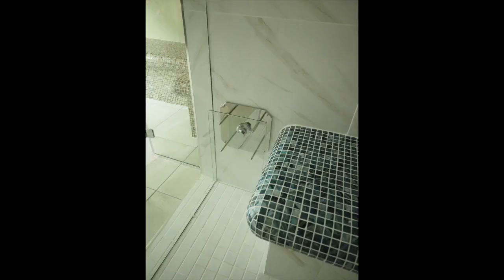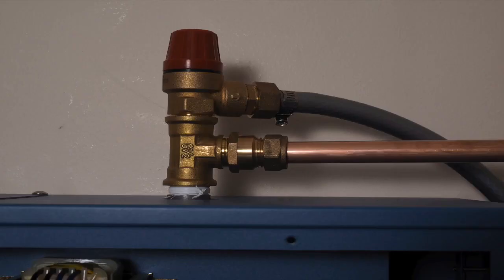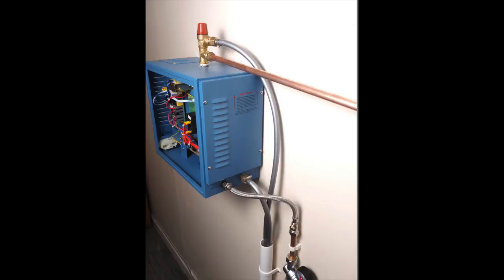The steam nozzle should be positioned 300 millimeters from the floor of the steam room and as far away from users' feet, a doorway, or the temperature sensor. In this image we show an example of how to pipe the top of the generator. The lower pipe which runs freely through the T-junction is the steam pipe which should be run in copper.